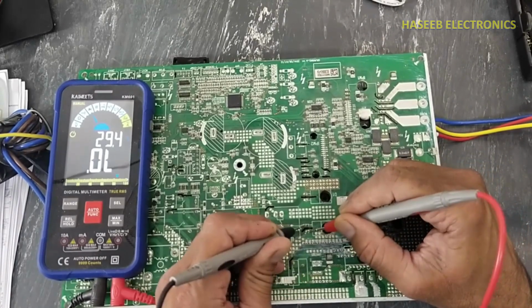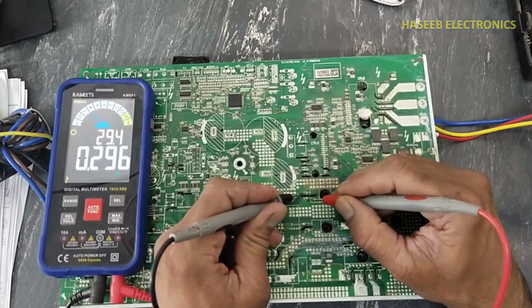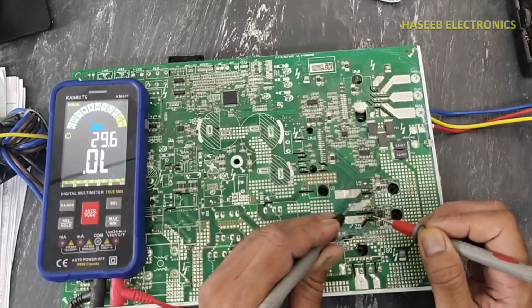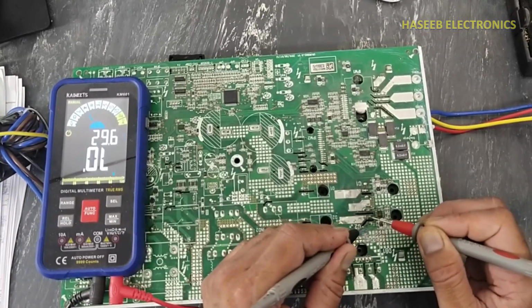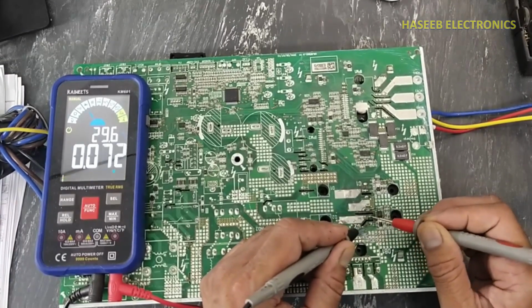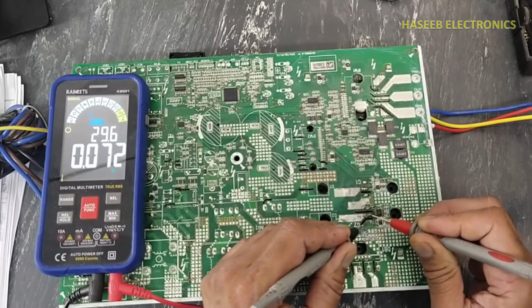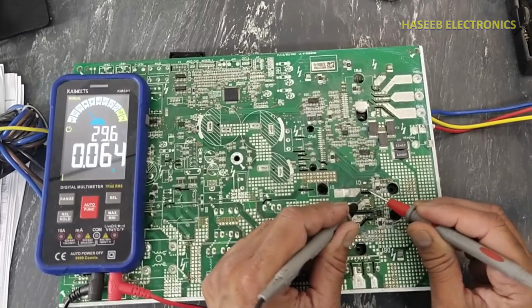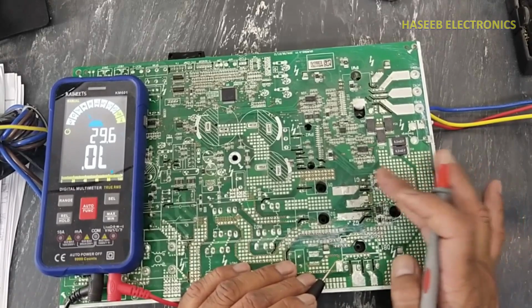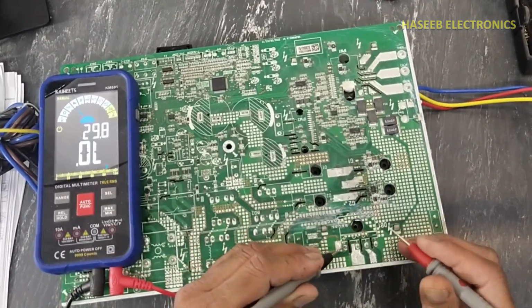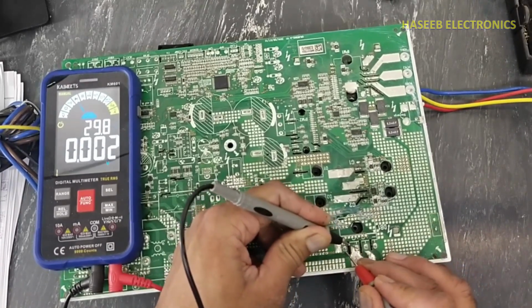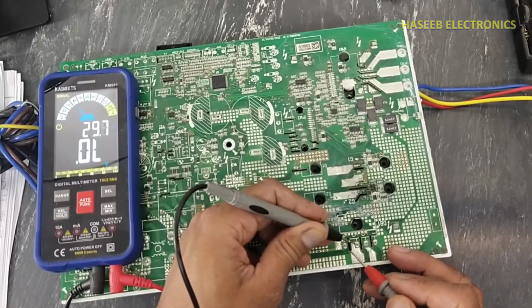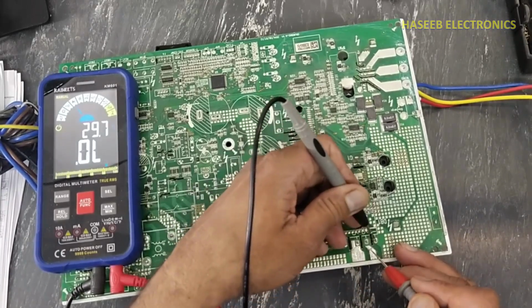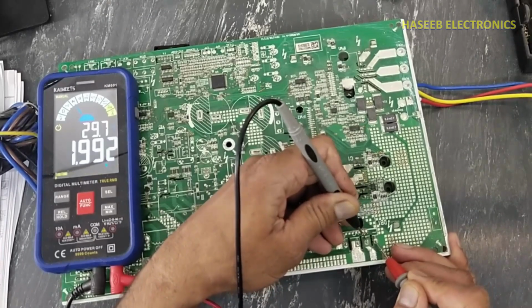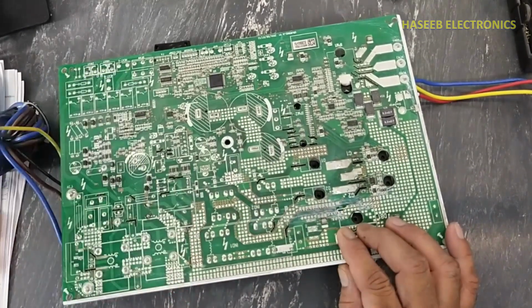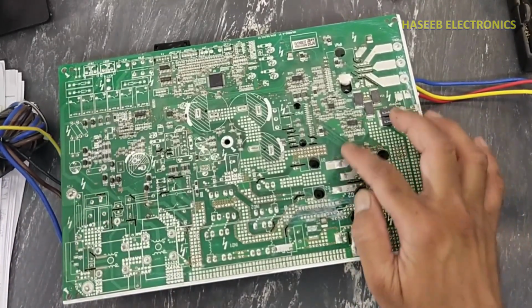Now check these diodes. Verify these IGBTs. So we need to remove these IGBTs. Connect the black lead at the bridge rectifier. This diode in the bridge rectifier is short circuit, so the bridge rectifier is also damaged. We will remove the bridge rectifier and we will remove these IGBTs.